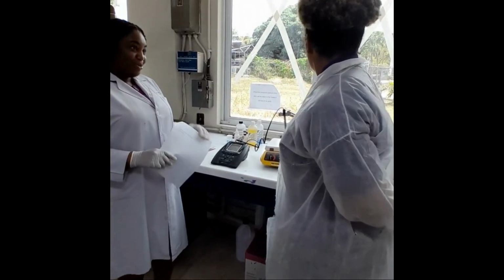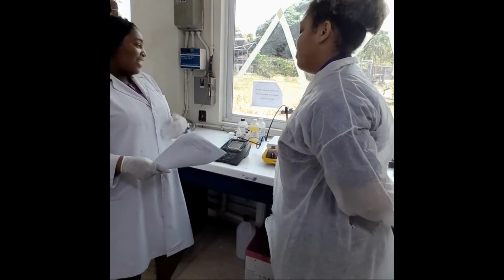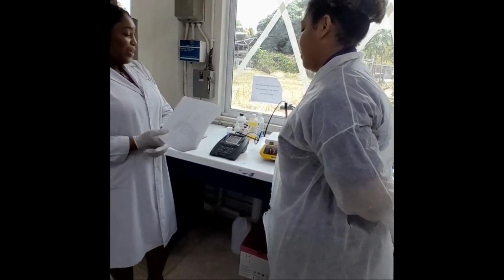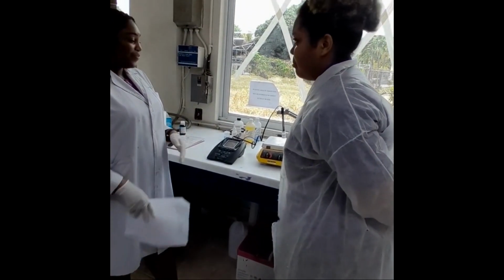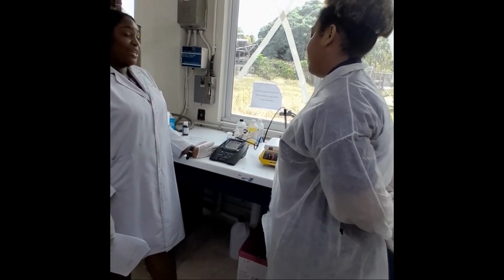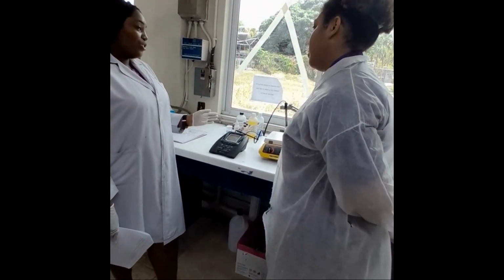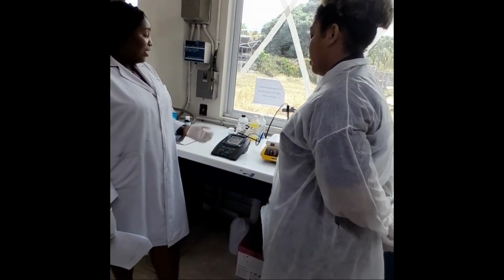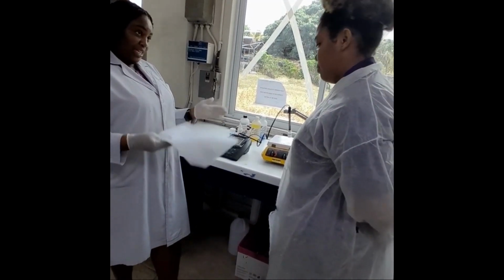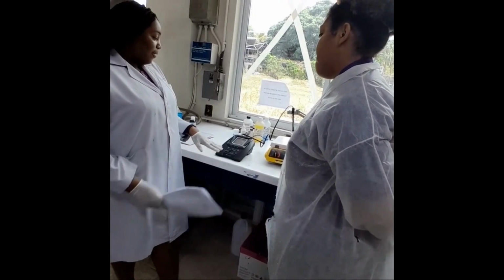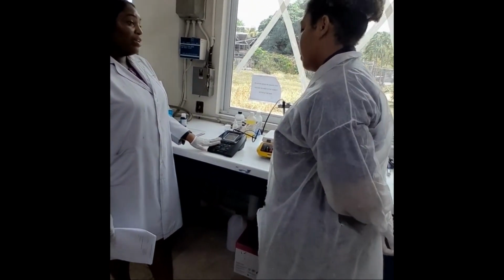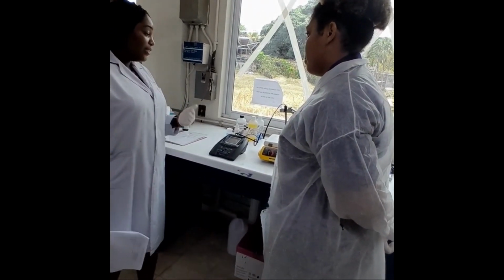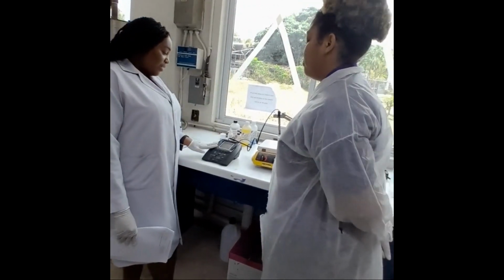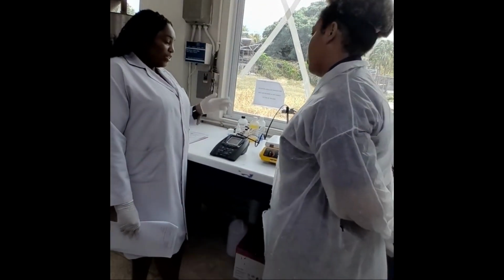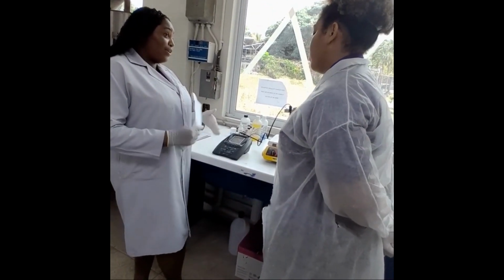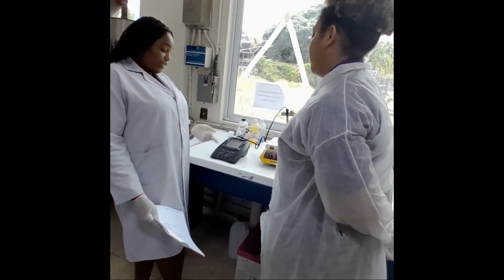You observe the material very well and you learn really quickly, and I guess your prior knowledge helped as well. So Latoya, while you're here as an intern, what we expect you to do is to be able to calibrate the pH meter. You should be able to select which buffers to use. Just remember, you will always get an expected pH, so you choose buffers within which that pH falls. Always remember to press calibrate when you're calibrating your pH meter. Whether it's in the buffers or the sample, allow it to stabilize and show ready before you take the reading. And always remember to wash your pH probe with distilled water and blot dry it before transferring from either buffers or samples or before storage.